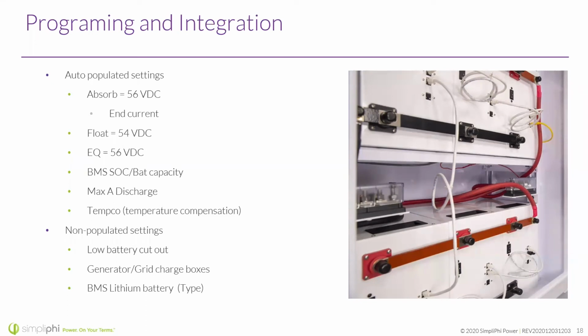And as I mentioned, at least with the Sol-Ark, we're looking at the BMS lithium battery type. So 00 is the type. All we do is just type that in, make sure that the BMS lithium battery is checked so that the system knows that a lithium battery is in place. Similar with the SMA, where we just need to let the system know that the battery that's being used is a lithium battery with comms.